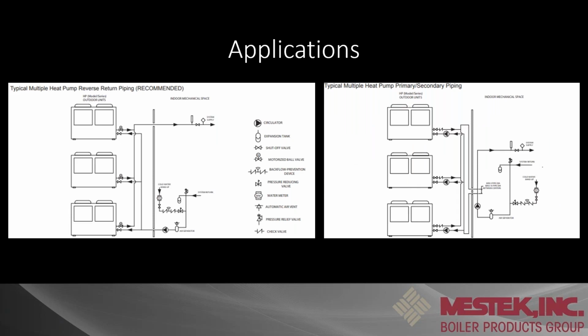Just a couple other little piping diagrams here. So over to the left here is your reverse return, recommended if we're doing multiple units. This one is one pump feeding multiple units, whether it's variable primary or not. There will be limitations if we were tying this into a variable primary system. Like I said, minimum flow of 44, maximum flow of 75 GPM. We really can't deviate from that. So just keep that in mind too if you're designing a variable flow system on the minimum flow rates.